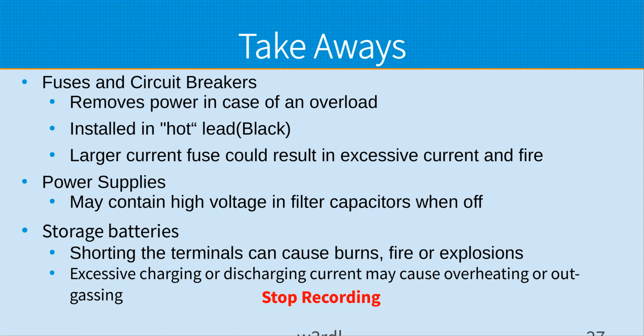Storage batteries: shorting them can cause extremely high currents, which can cause burns, fires, explosions due to the outgassing and overheating, overpressure. It's pretty much a sealed unit, so when you really heat it up, you get a lot of pressure inside.